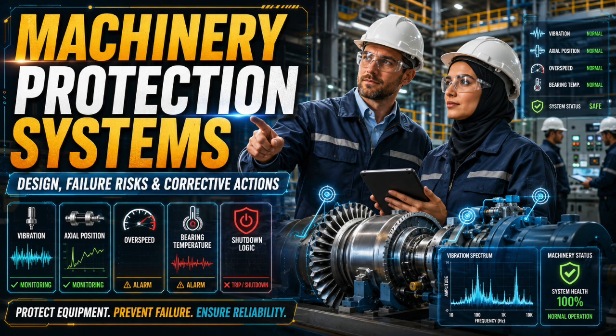Monitoring tells you something is happening. Protection decides when continued operation is no longer acceptable, and that decision must be reliable. Let's break this down in a practical way. When you specify radial shaft vibration, you are trying to understand rotor movement relative to the bearing system. This is critical for machines with fluid film bearings, turbines, compressors, large pumps, and similar rotating equipment. The rotor may show imbalance, misalignment effects, oil whirl, oil whip, rubs, looseness, instability, or abnormal dynamic behavior.